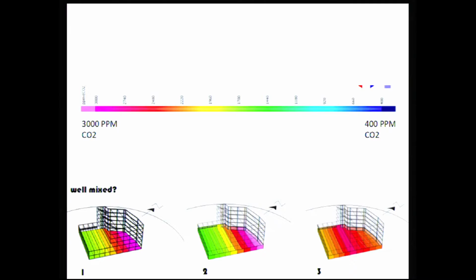And in case Hal asked a question about ppm, here we can see 3,000 ppm on the left and 400 ppm on the right. And so the question is, have we solved the problem? Well, no, not yet. We need more fresh air, and probably we need to design for not the absolute max allowable occupancy by fire code, but rather a more reasonable, regular, everyday occupancy.